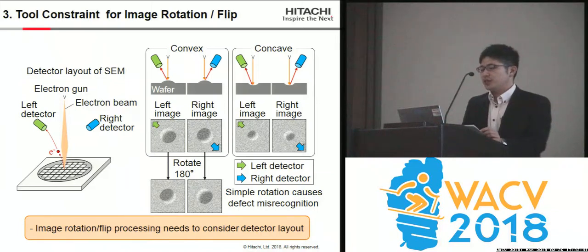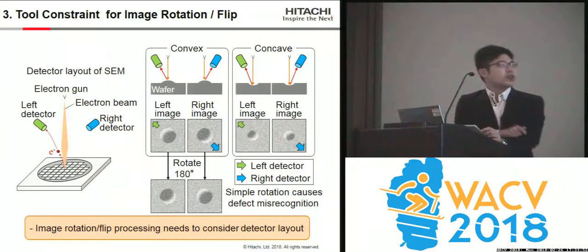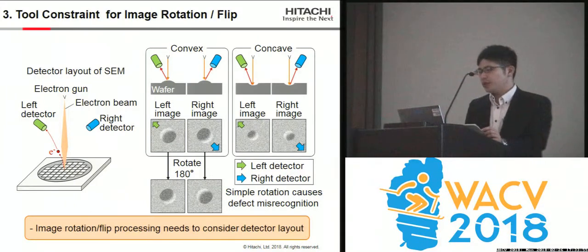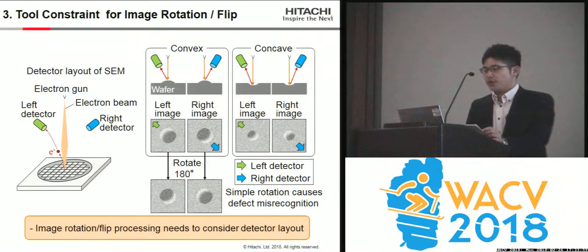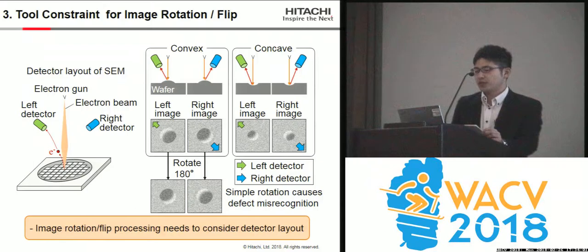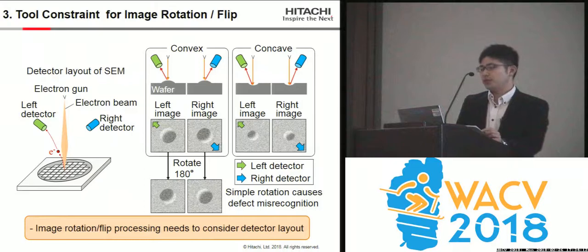SEM images are seen as if they were illuminated from the detector directions. As you can see, the left image of a convex defect is similar to the right image of a concave defect. Therefore, if the convex images are simply rotated, they become almost the same as the concave images. Since the ADC recognizes defect topography on the basis of these images, simple rotation causes defects to be misrecognized.